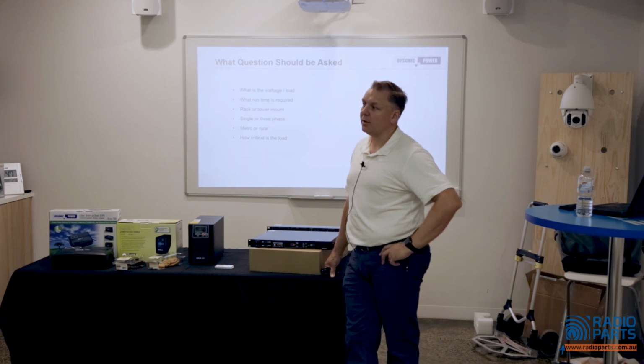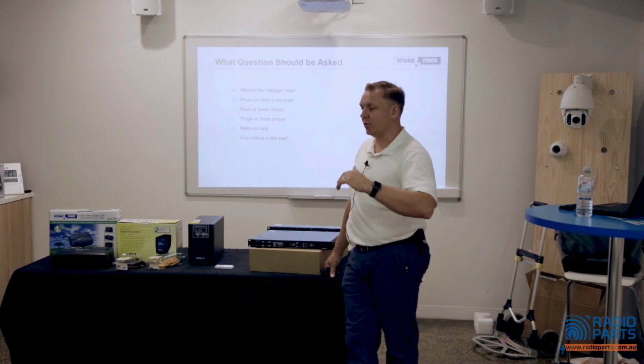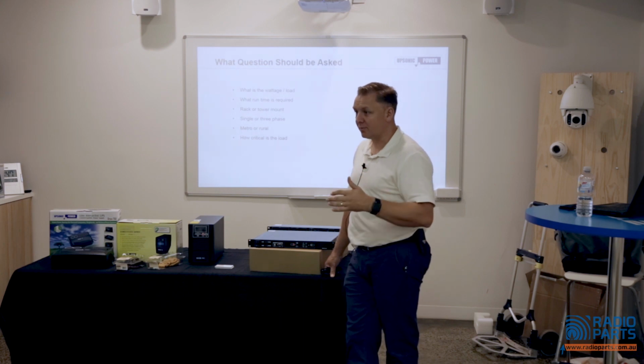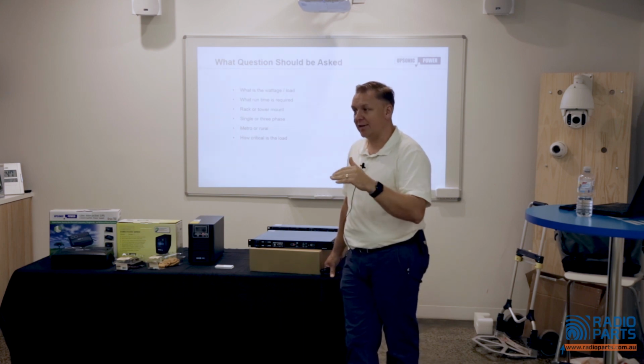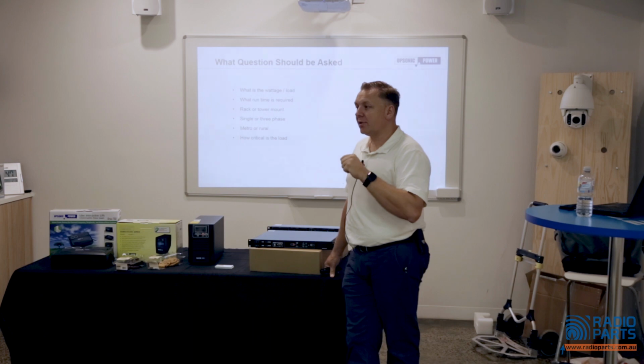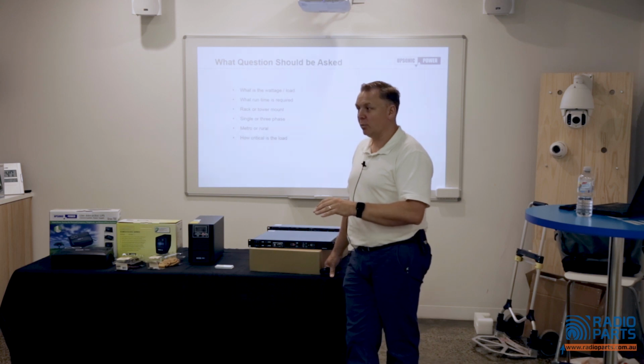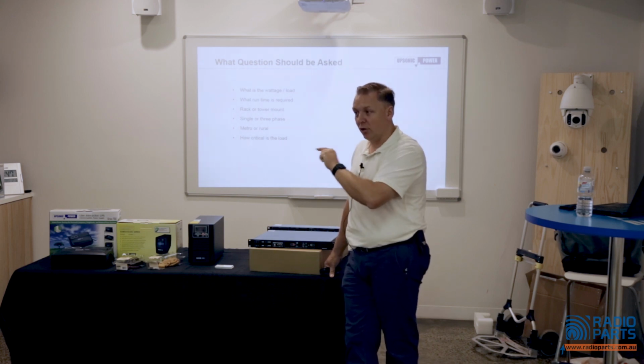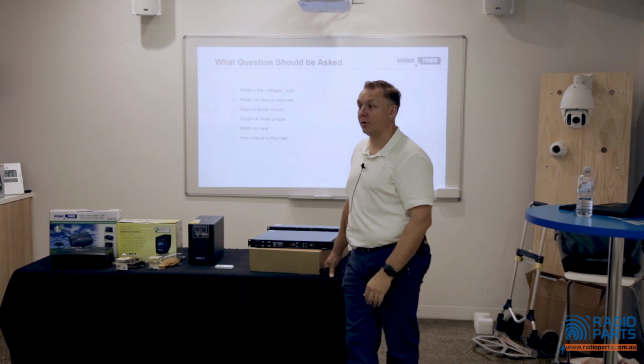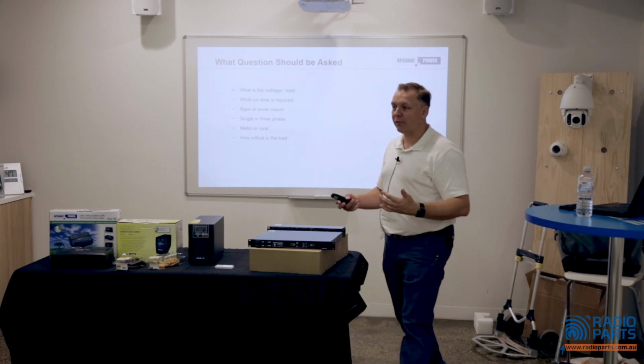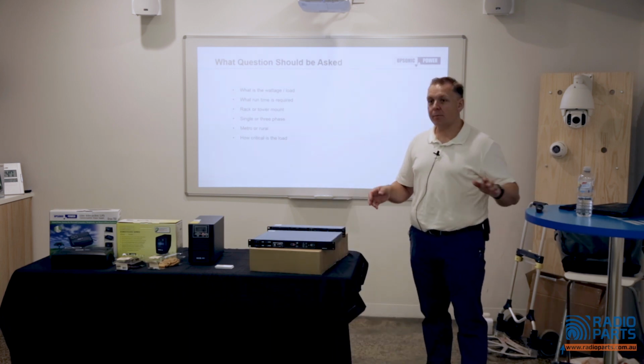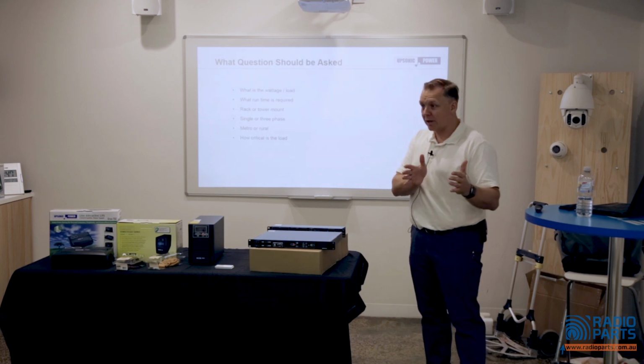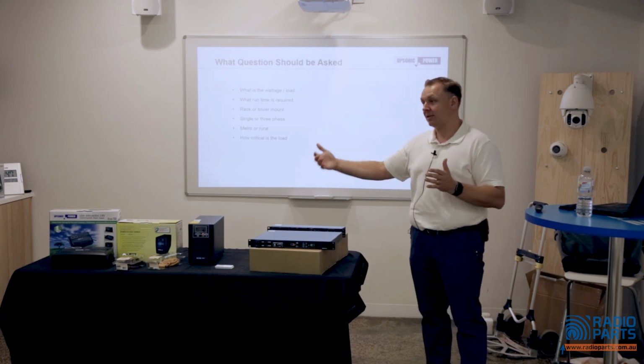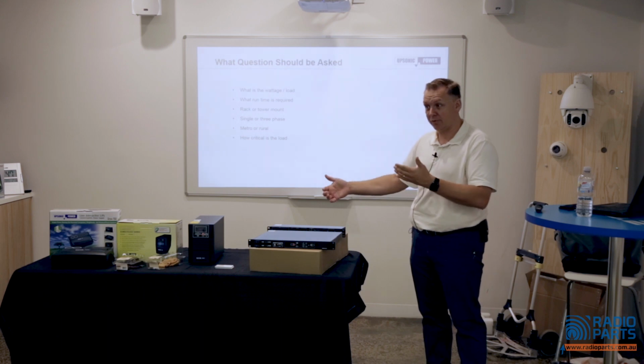There is, and that gets back to performance and reliability standards. You will find almost all UPS suppliers, even when we supply for a medical application, will explicitly state not for life-saving performance. So typically for anything that critical, the actual device itself will have its own battery backup, which is then supplemented by a UPS. So again, we're talking about levels of redundancy.